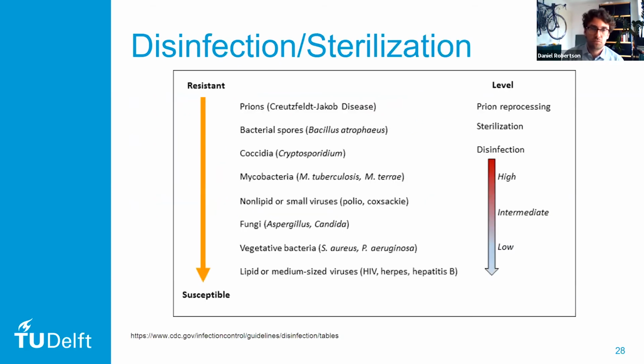Okay, so what is actually the difference between disinfection and sterilization? The difference is that sterilization kills anything up to and including bacterial spores, whereas disinfection kills anything lower than that. And we have differences in levels of disinfection. So we have high-level disinfection, intermediate-level disinfection, and low-level disinfection. Now, low-level disinfection is for instruments that only come into contact with the patient's skin.